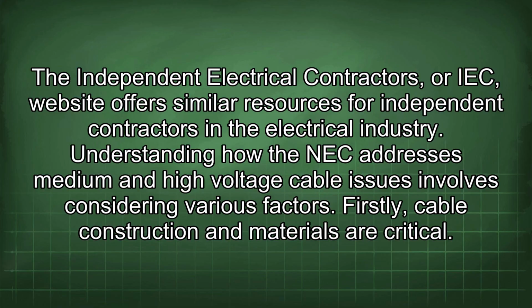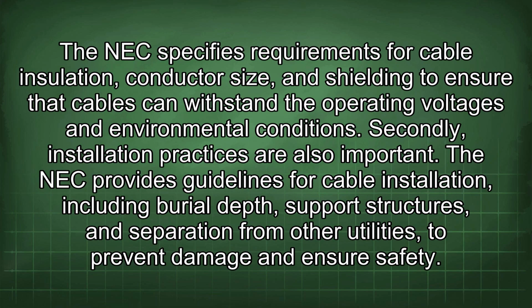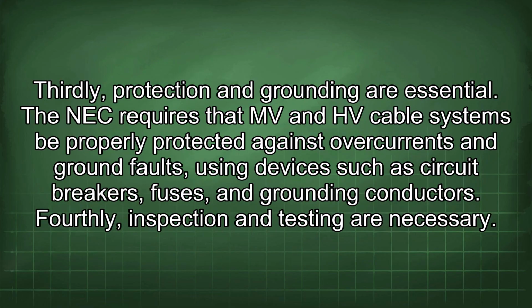Understanding how the NEC addresses medium and high voltage cable issues involves considering various factors. Firstly, cable construction and materials are critical. The NEC specifies requirements for cable insulation, conductor size, and shielding to ensure that cables can withstand the operating voltages and environmental conditions. Secondly, installation practices are also important. The NEC provides guidelines for cable installation, including burial depth, support structures, and separation from other utilities to prevent damage and ensure safety.